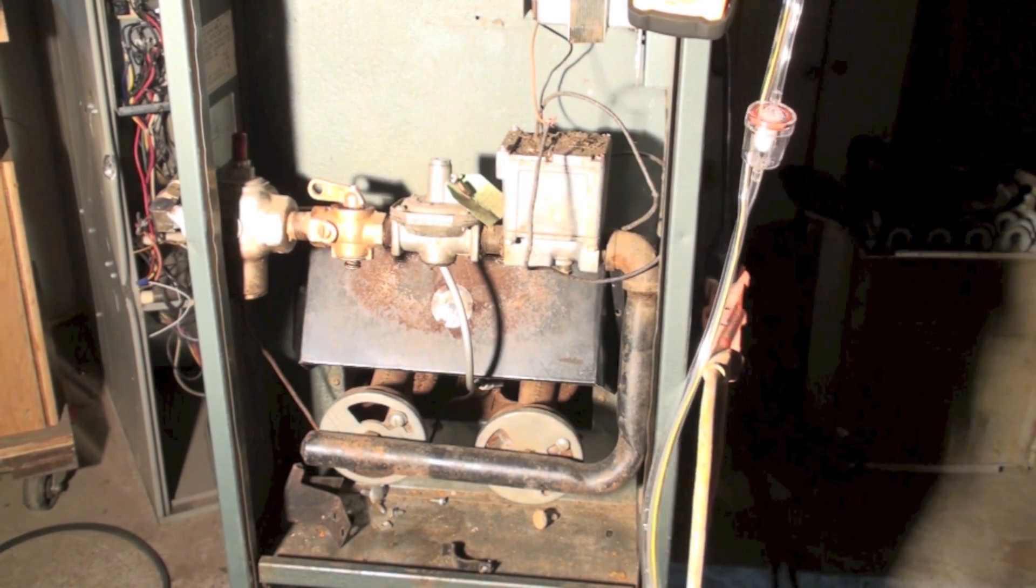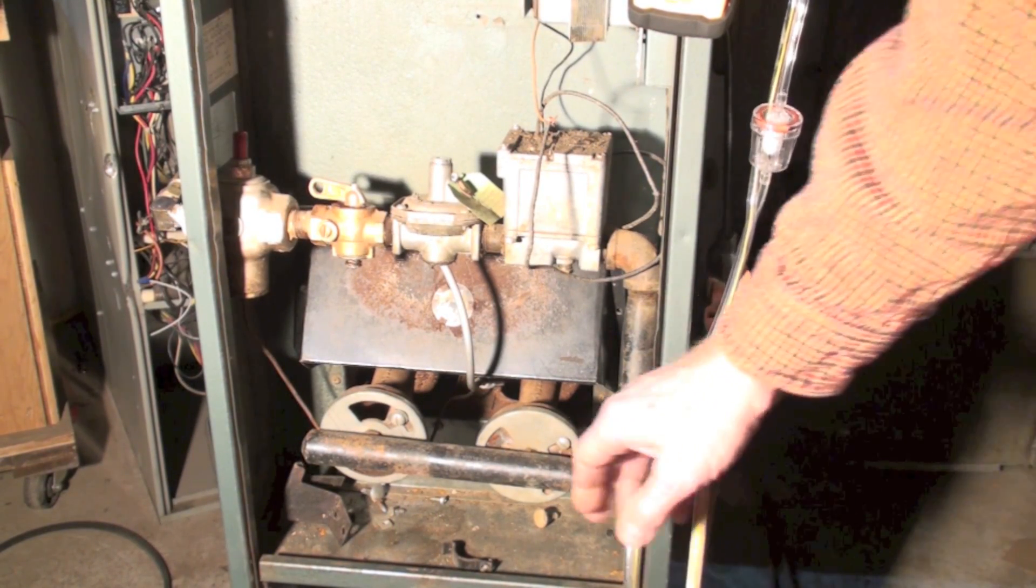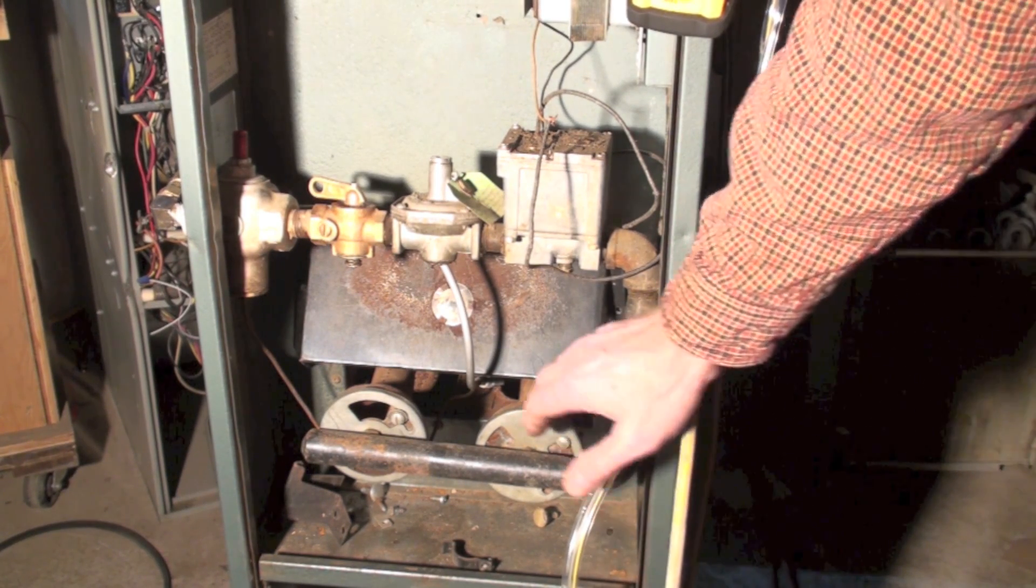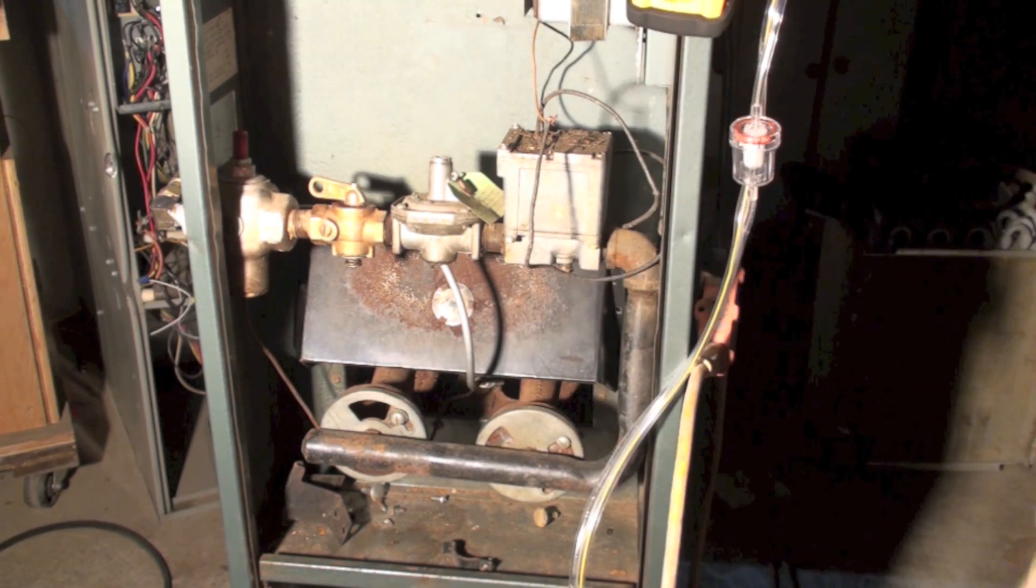Okay, the first thing I wanted to note was the burner on the right - I've closed off the primary air completely. The burner on the left is wide open.